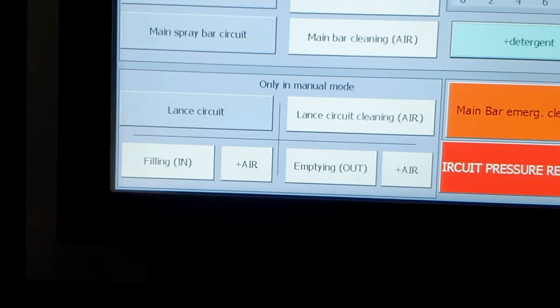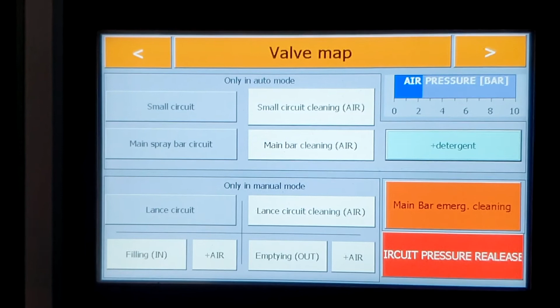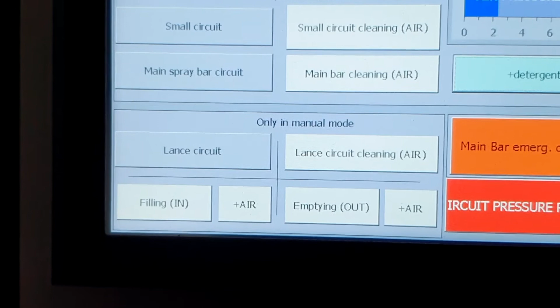Now below we've got the lance circuit, filling in and emptying from the emulsion tank. Please also take a close look that these modes for the lance are only available in manual mode, and this manual mode is chosen by this switch. And the modes for the spray bar, which are above, are only available in auto mode, so you will not be able to start the small circuit if this switch is on manual mode.